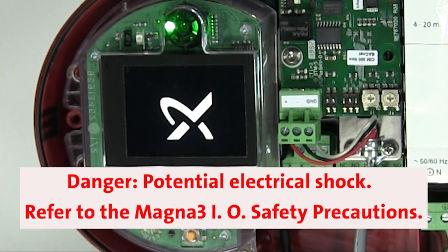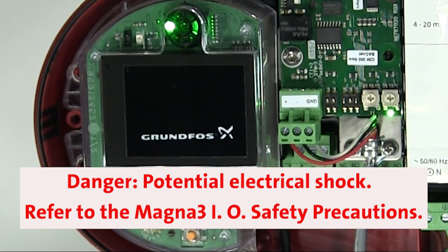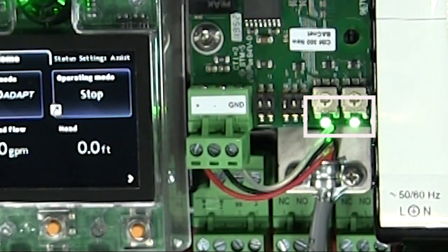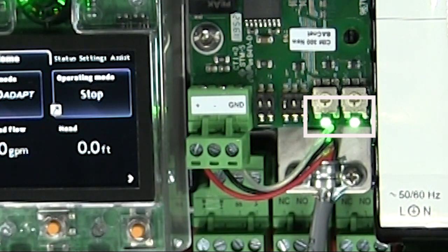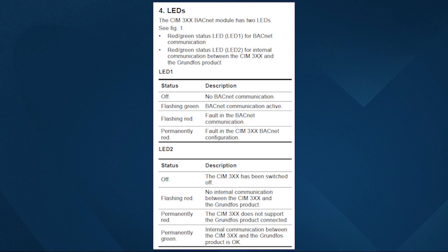Step six is to confirm that the card is communicating with the network, so we'll power on the MAGNA-3 to demonstrate communication. The CIM300 BACnet module has two LEDs: LED 1 on the left is for BACnet communication, and LED 2 on the right is for internal communication between the CIM300 and the Grundfos pump. Here we can confirm that LED 2 is permanently green and the BACnet LED is flashing green, indicating that we are communicating with the network. If you have any questions about the functions of the LEDs, see section 4 on page 5 of the CIM300 BACnet module I.O..